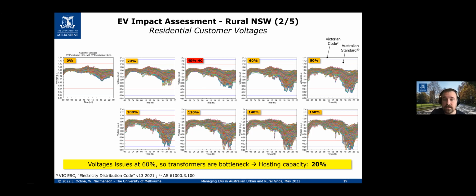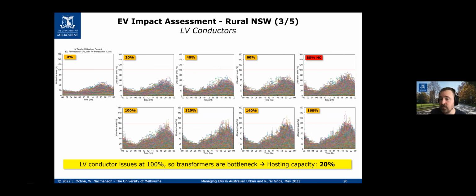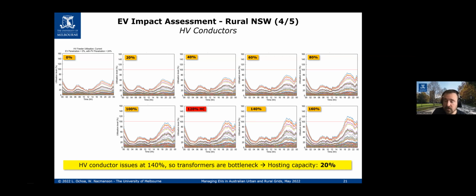So if we move on to the next slide, please. The same story now appears with the LV conductors. With LV conductors, we can host even more without problems, but those other problems need to be solved if we want to achieve higher hosting capacities. And finally, if we look at the HV feeder utilization, we can go every house with an EV for this feeder without causing HV conductor issues. If you want to get there, you have to solve voltages, LV conductors, and LV transformers. So ultimately, there will be a bottleneck for every feeder. That is the problem you encounter first. That will vary feeder to feeder, region to region. And in this case, we hit our first bottleneck at 20%, which is the LV transformers.